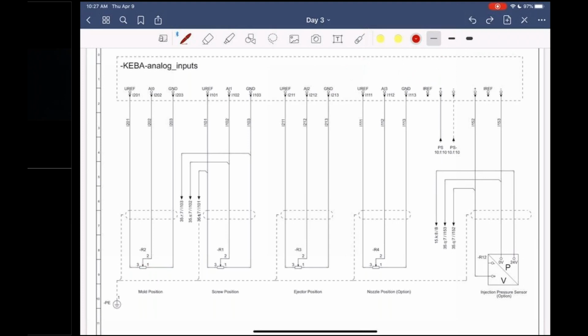These are analog signals. An analog signal is anything that has a range 0 to 10. A digital signal is anything that has 0, on or off status. There's no other status in between for digital except for on and off. For example, when you turn a light on, that's a digital signal. It only goes on and off, unless you're having a dimmer, which would be analog.